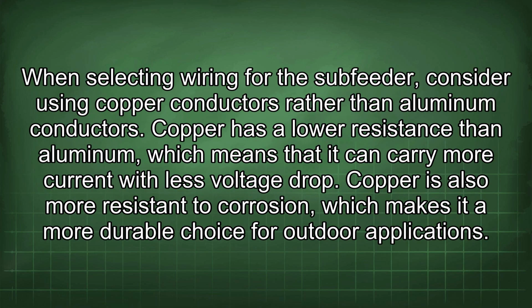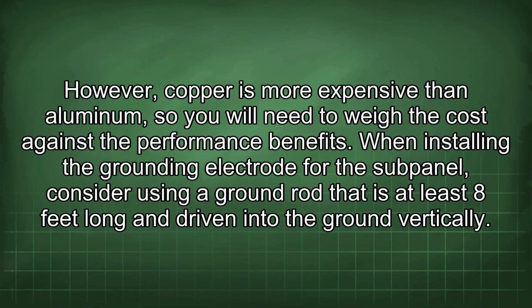When selecting wiring for the subfeeder, consider using copper conductors rather than aluminum conductors. Copper has a lower resistance than aluminum, which means that it can carry more current with less voltage drop. Copper is also more resistant to corrosion, which makes it a more durable choice for outdoor applications. However, copper is more expensive than aluminum, so you will need to weigh the cost against the performance benefits.